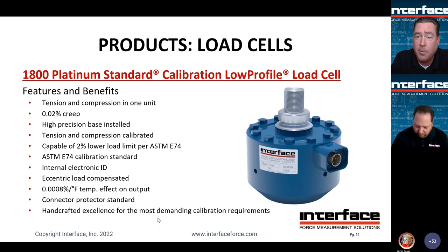As Brian mentioned, there is a grade above the 1600, where we take it even farther. The positive benefits of the installed calibration adapter are built upon with this load cell. It's a monolithic design, so the thread adapter in this case is actually integral to the load cell. So there's no threaded joint inside that load cell, which further improves repeatability, as Brian referenced earlier. This load cell also has twice the number of gauges than one would find in our standard 1600 series. This has the added benefit of further reducing sensitivity to off-axis or moment loading by better balancing the bridge across the load cell.